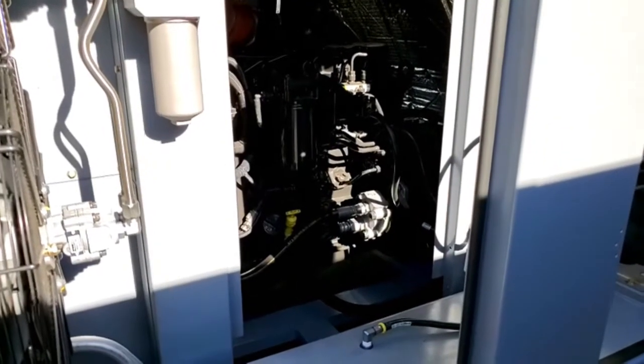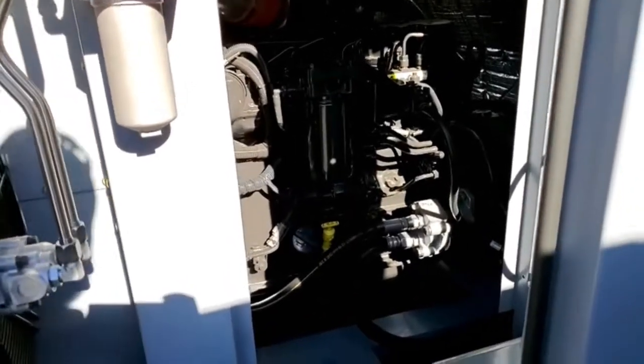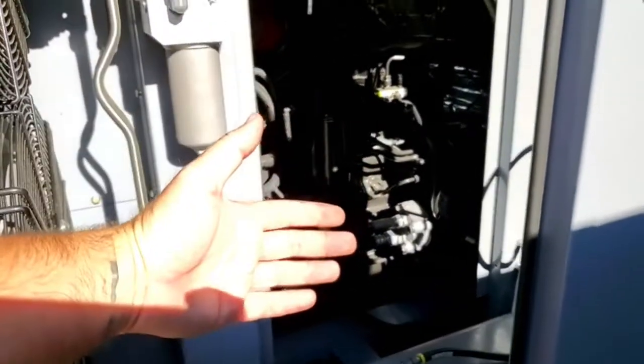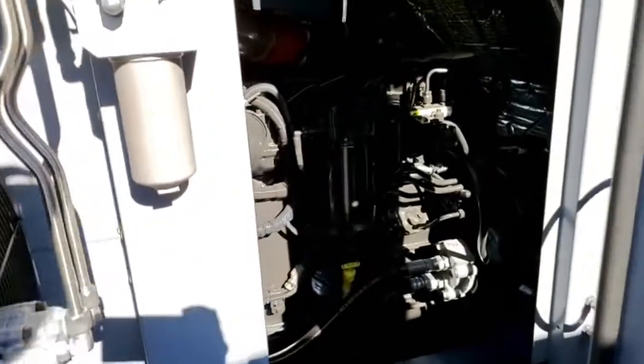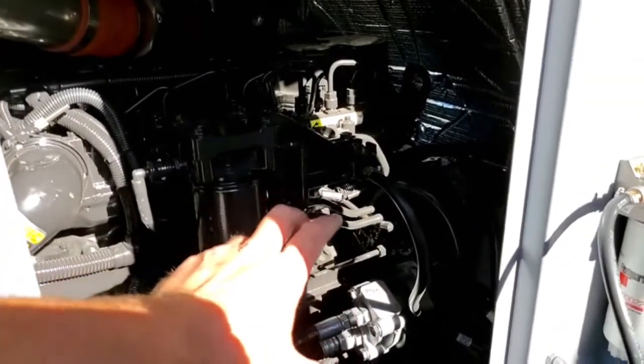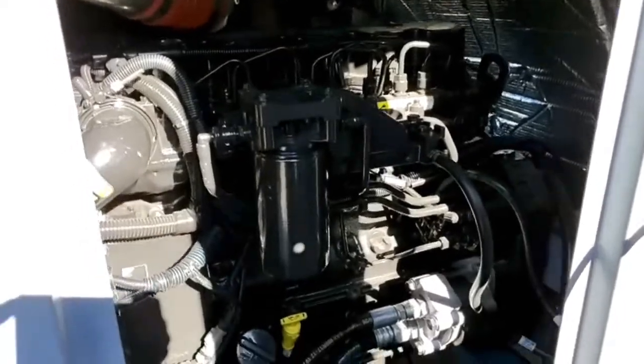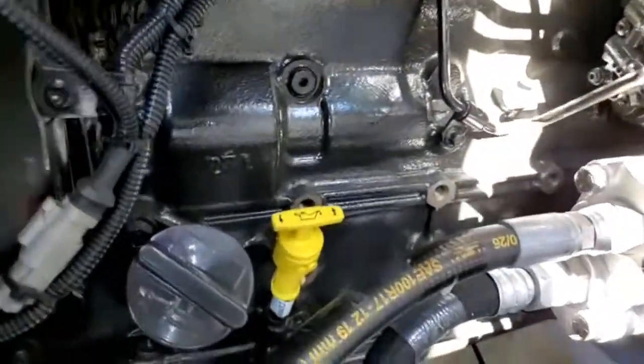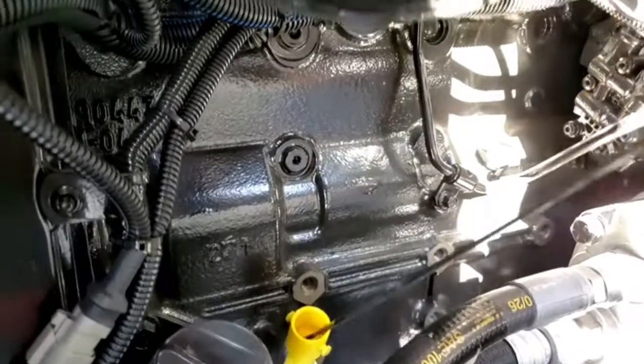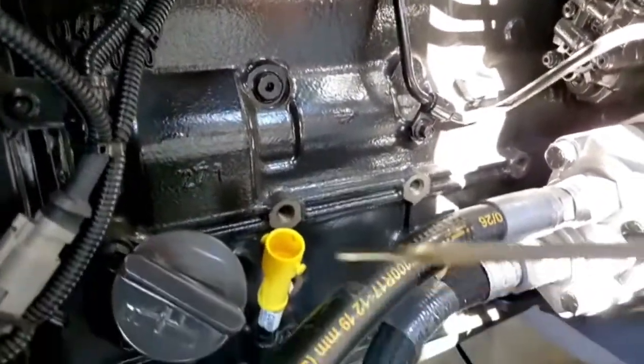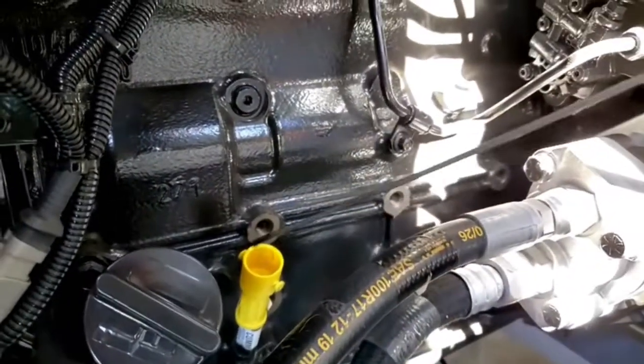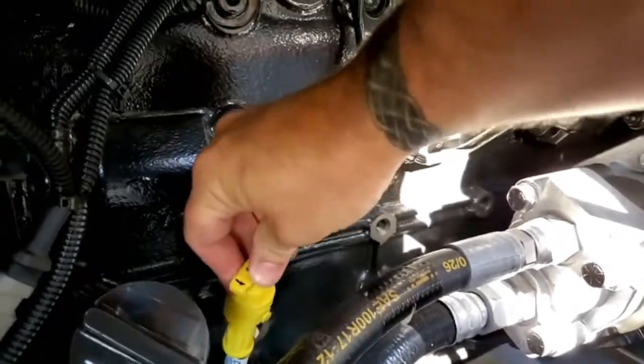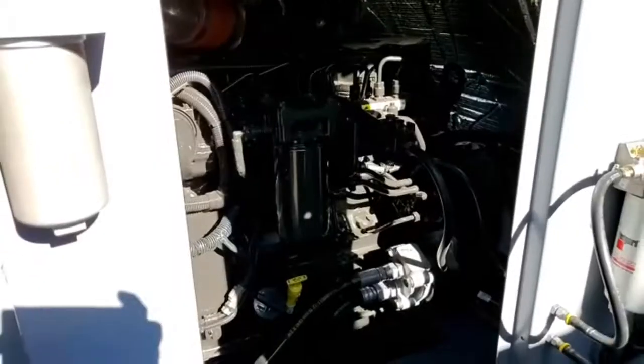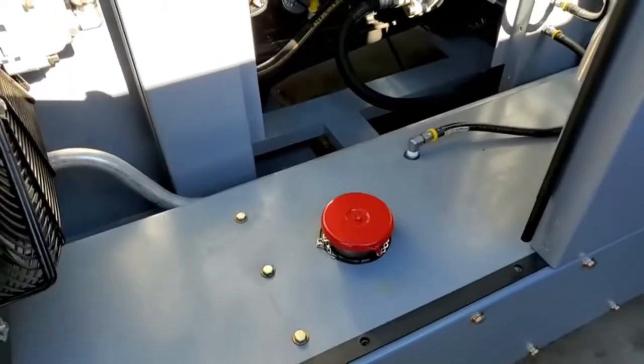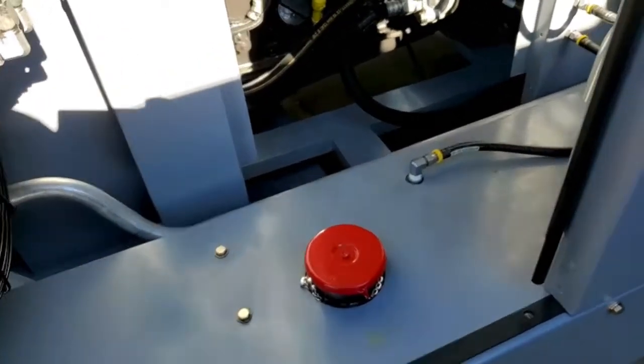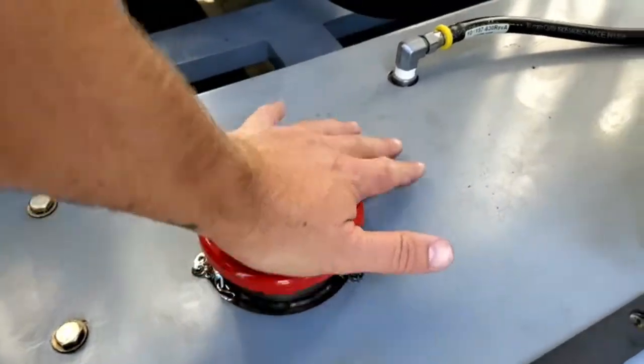Here we're on the left side of the unit. We don't have any panels on here, so you would actually have to open this access panel door and then either open the small access panel for the engine or remove this whole panel altogether. So in here you can check your engine oil. Make sure it's at the proper operating level. You're also going to remove this cap to service the fuel tanks with diesel.